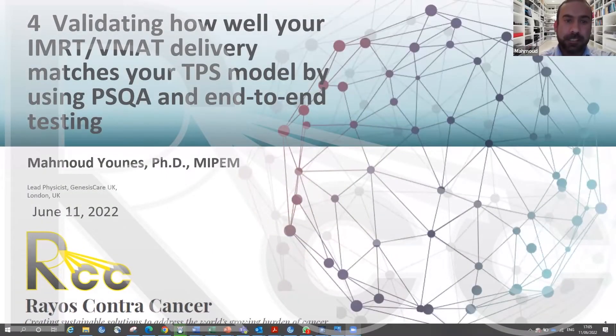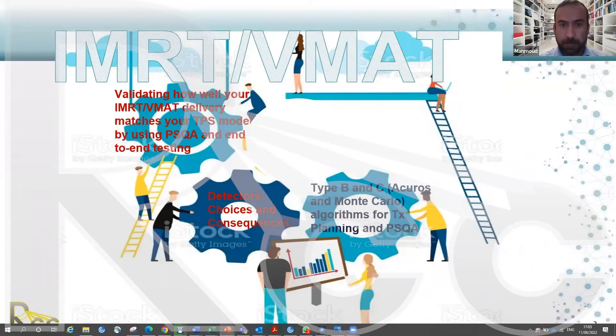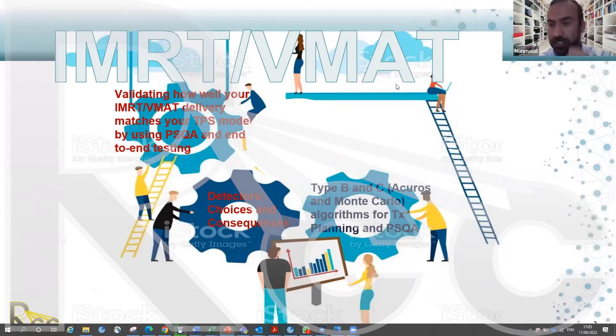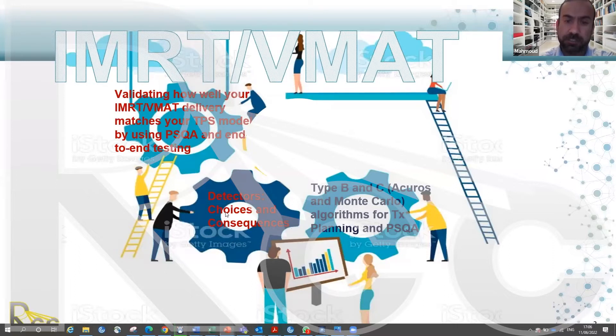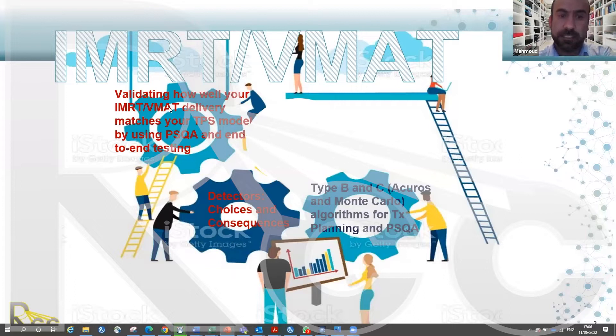We are talking today about validating how well your IMRT and VMAT delivery match your TPS model by using patient-specific QA and end-to-end testing. This is a standalone presentation in a group of presentations to build our IMRT and VMAT technique in our center. We started with type B and type C algorithms and detectors in previous sessions, and today we are validating how well IMRT delivery matches our QA and TPS model.